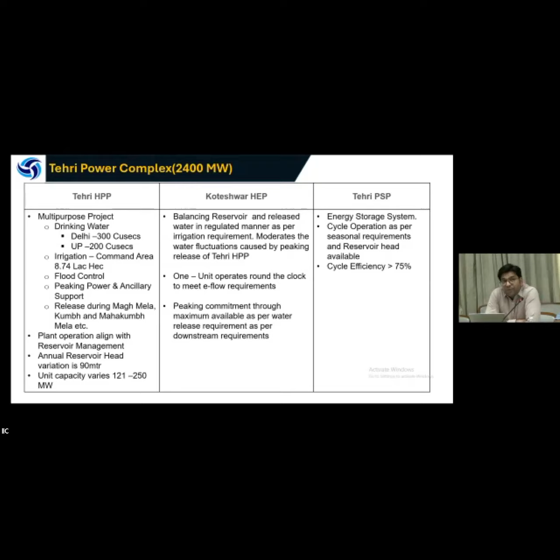And the Tehri PSP is the energy storage system. The cycle operation is as per the seasonal requirement and the reservoir head available. The cycle efficiency is higher than 75%, around 80%. And this is the operation philosophy of the plant, in which the operation of the Tehri PSP is formulated honoring the operational commitments of the HPP and KHEP.